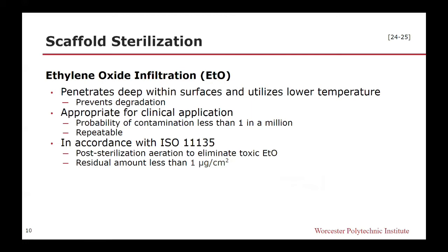This method of sterilization meets international standards, which require the probability of contamination to be less than 1 in a million. Terminal sterilization ensures this higher degree of sterility and is repeatable. To ensure our sterilization is in accordance with ISO 11135, we plan to use a procedure proposed by Monaco et al.